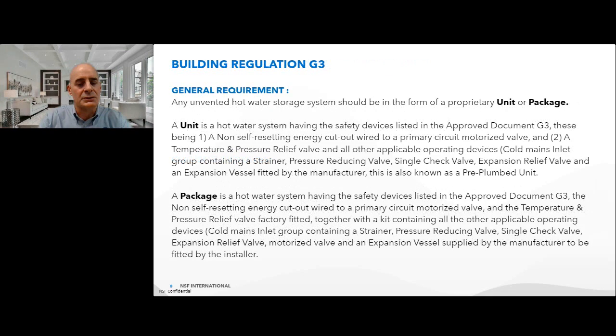The general requirements then is that an unvented hot water storage system should be in the form of a proprietary unit or package. A unit, the hot water system, having the safety devices listed in the approved document G3, so these being the non-self-resetting energy cutout wired to a primary circuit motorized valve and a temperature and pressure relief valve, and all of the rest. So this will then contain the strainer, pressure reducing valve, single check valve, expansion relief valve, and expansion vessel fitted by the manufacturer. So this is known as a pre-plumbed unit.